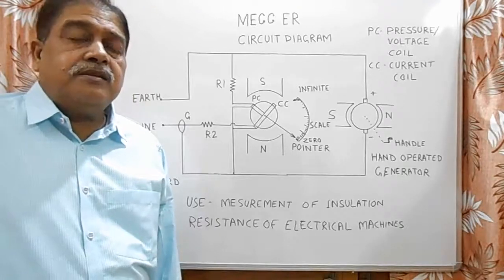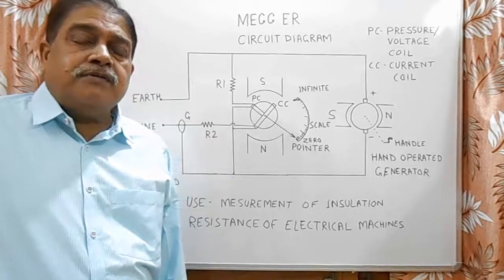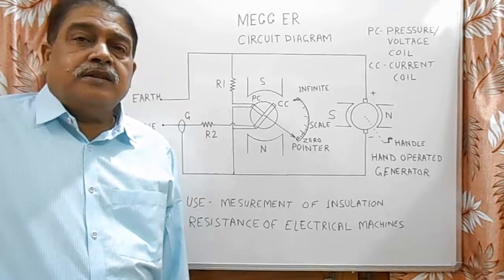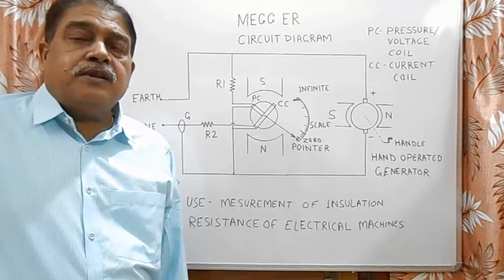For any motor, Megger value must be its supply rated voltage multiplied by 1000. That is for example, 400V motors, it must be 400 multiplied by 1000.